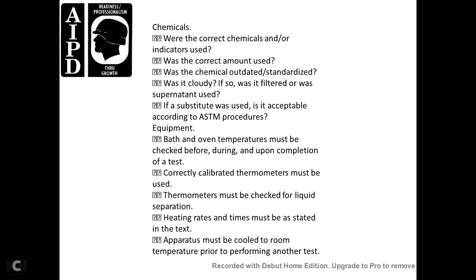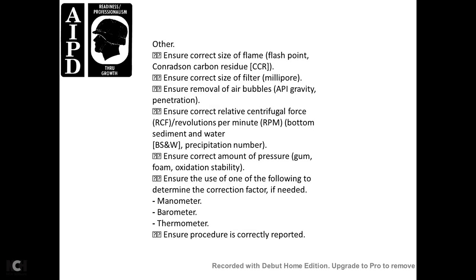Equipment: bath and oven temperatures must be checked before, during, and upon completion of the test. Correct calibrated thermometers must be used, checked for liquid separation. Heating rates and times must be stated within the test method. Apparatus must be cooled to room temperature prior to performing another test. Ensure correct flame size for flash point and Conradson Carbon Residue (CCR); correct filter size for millipore; removal of air bubbles for API gravity and penetration; correct RCF revolutions per minute for bottom sediment and water.